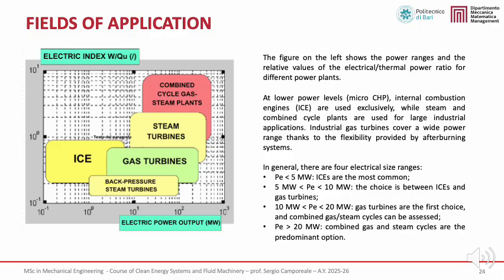The chart on the left shows how different cogeneration technologies are distributed over a wide range of electrical power outputs. The horizontal axis represents the electrical power output, while the vertical axis represents the electric index, defined as the ratio between electrical and useful thermal power. At low power levels, typically in the micro CHP and small scale range, internal combustion engines are the dominant solution. This is mainly due to their high electrical efficiency, good part load behavior, and strong operational flexibility, which make them well suited for decentralized applications.